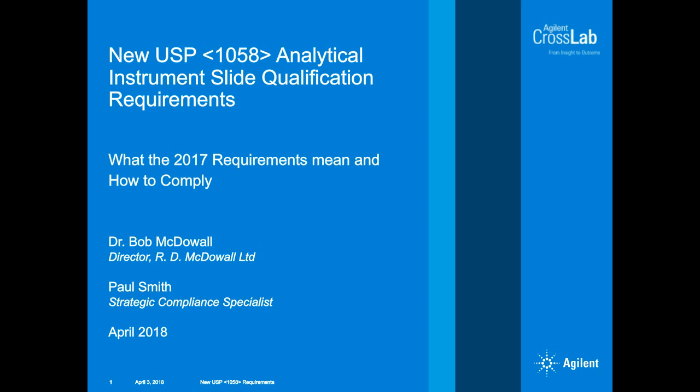So do we need to write a URS? Yes, you do. Because of data integrity, this will not be minimal. Again, you'll find more information on the Spectroscopy Online publication that will come out this month in my Focus on Quality column, where we talk about URS, and I give you more examples of that. I'll pass over to Paul.